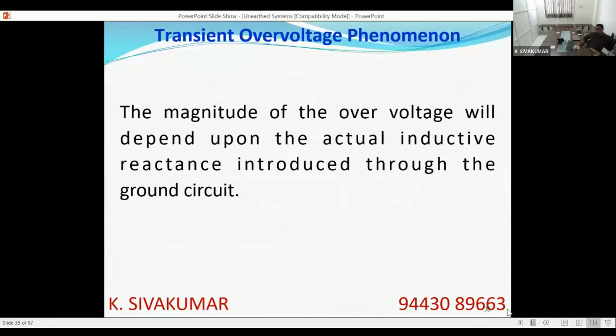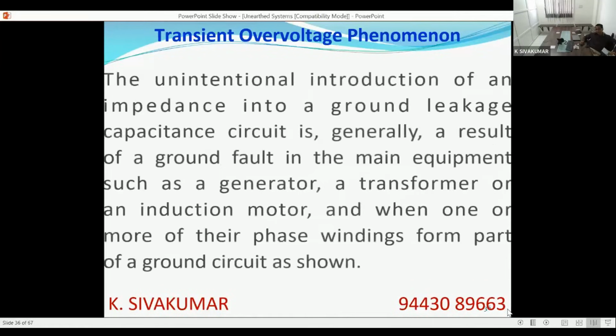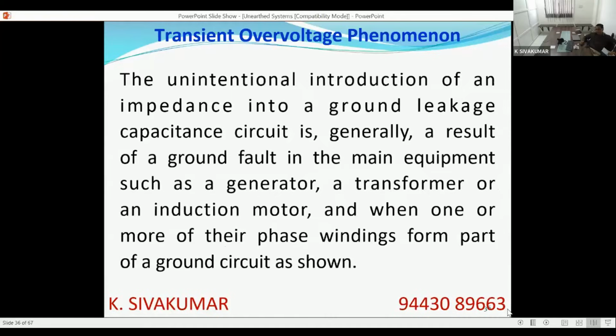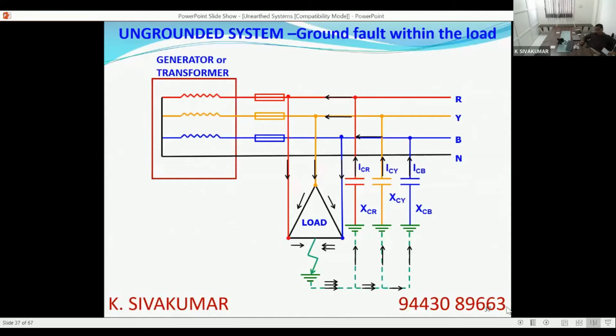So the magnitude of over voltage, there are precise calculations available which we will see, will depend upon the actual inductive reactance introduced in the circuit. What is the content of the inductive reactance? Now, the unintentional introduction of an impedance in a ground leakage capacitance circuit is a result of a ground fault in the main equipment such as generator, transformer or induction motor. When any of these windings get earthed like this.